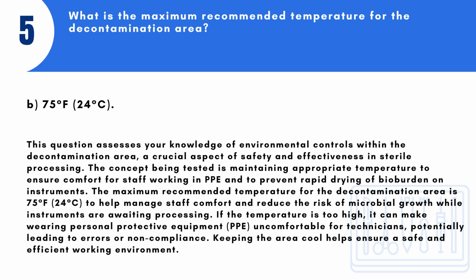The maximum recommended temperature for the decontamination area is 75 degrees Fahrenheit, 24 degrees Celsius, to help manage staff comfort and reduce the risk of microbial growth while instruments are awaiting processing. If the temperature is too high, it can make wearing personal protective equipment, PPE, uncomfortable for technicians, potentially leading to errors or non-compliance.